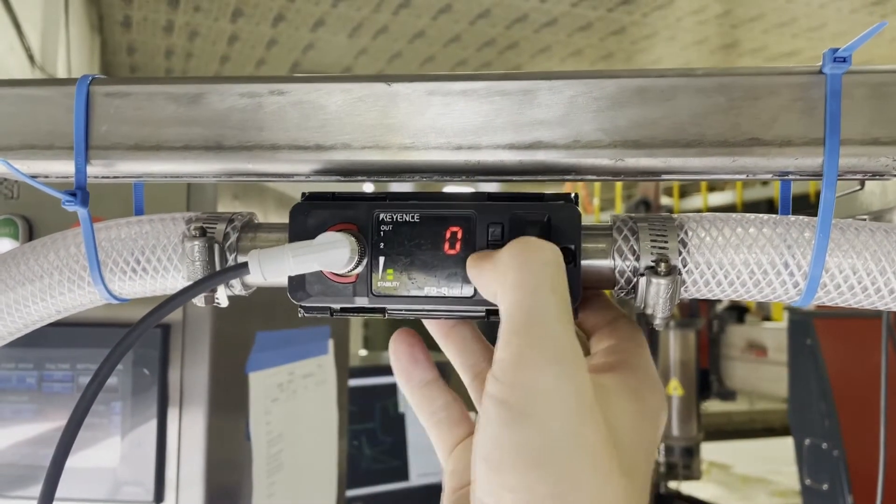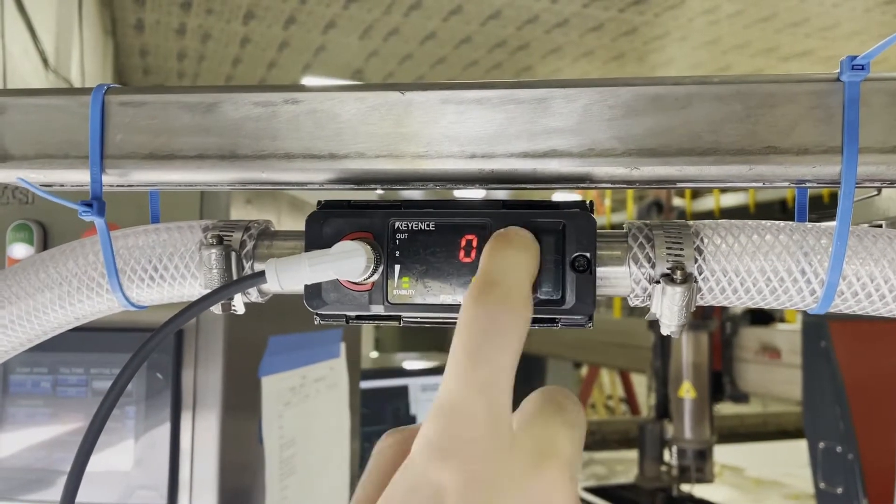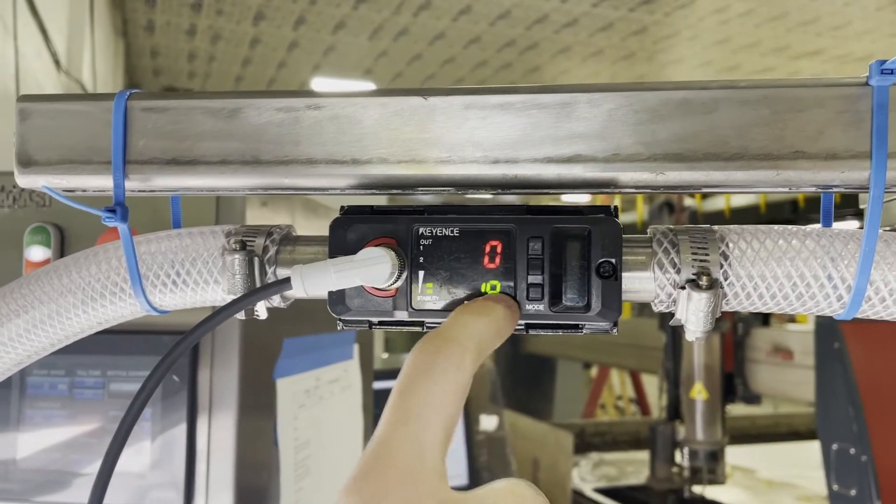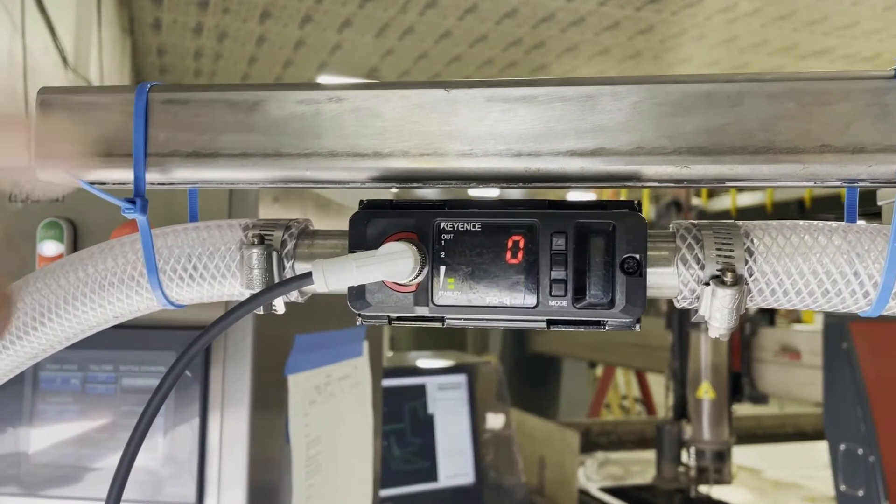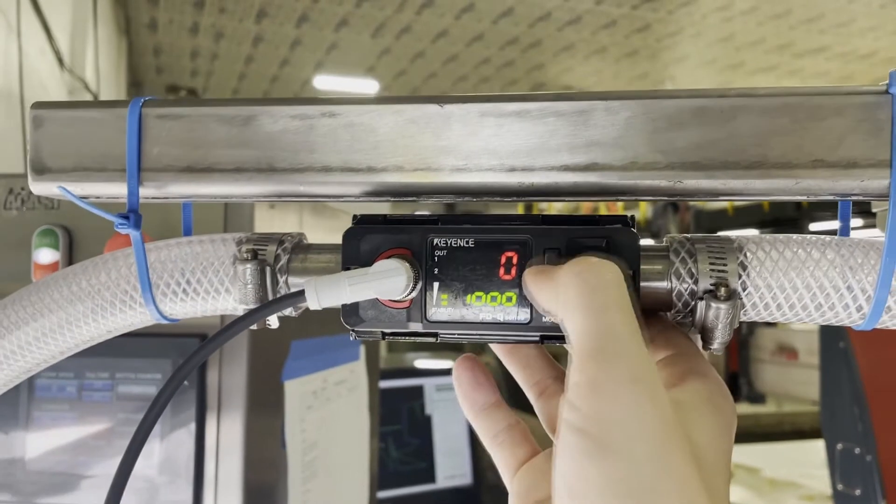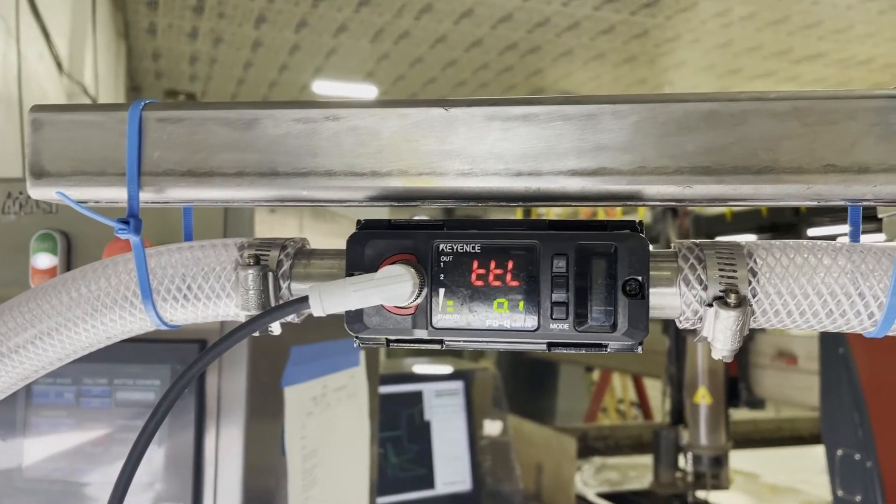I'm going to keep on scrolling. This is the total. How do I want my total to read on the screen? As in 10.1 gallons or just 10? Or I can have it read every 10 gallons or every 100 gallons on the screen. We're doing liters, right? So it will be 0.1. All of this is in liters. Correct. So in your case, you're using the pulse output. So I'm going to have it in 0.1. Perfect.